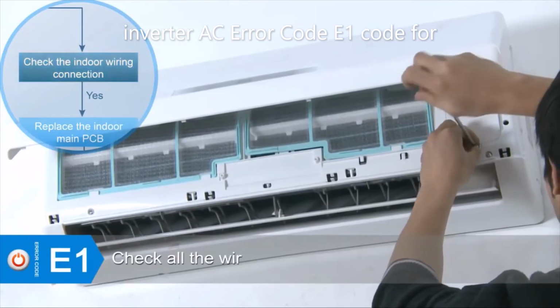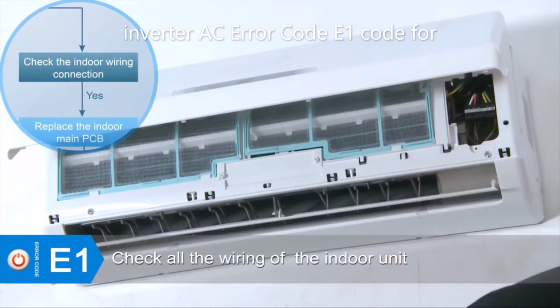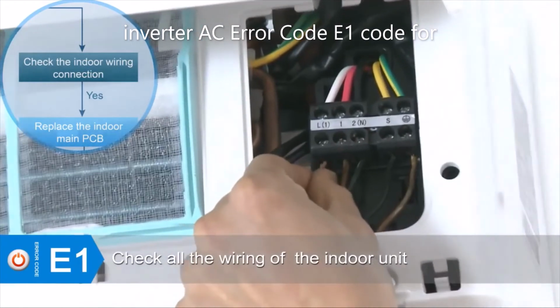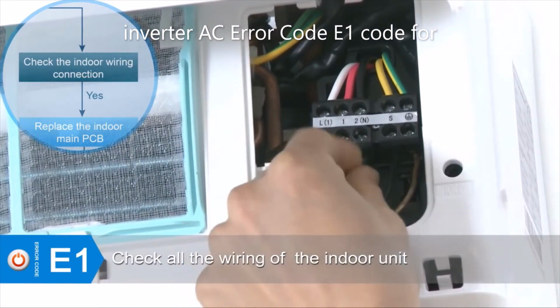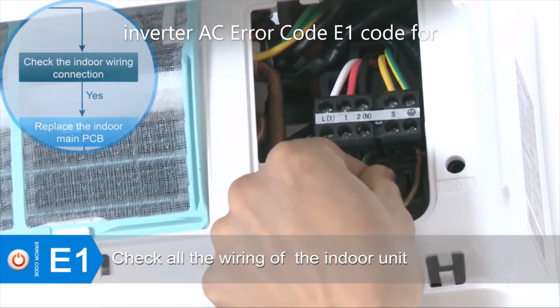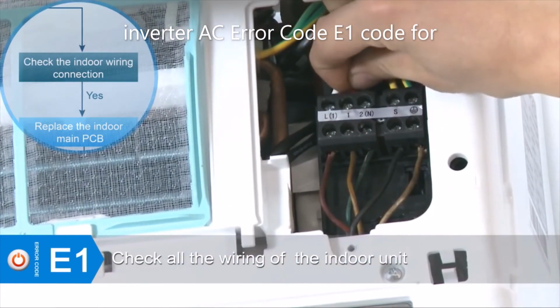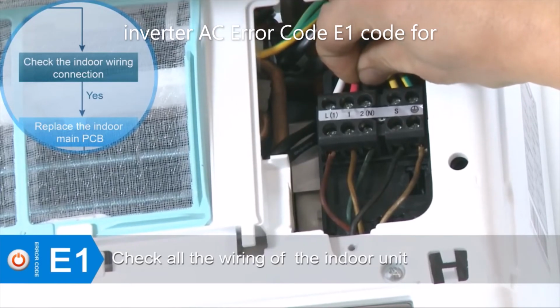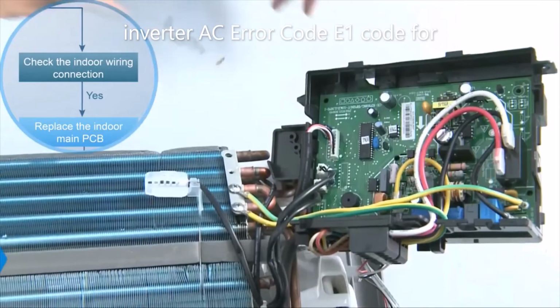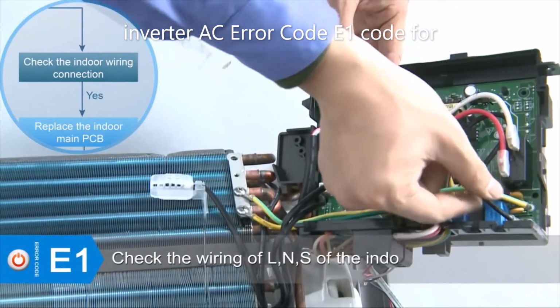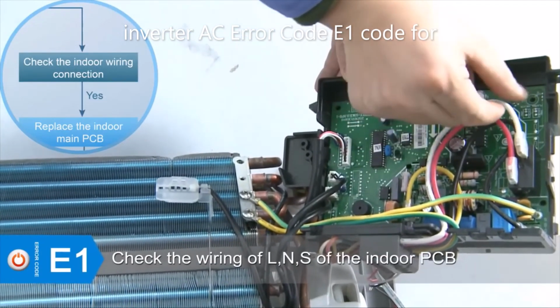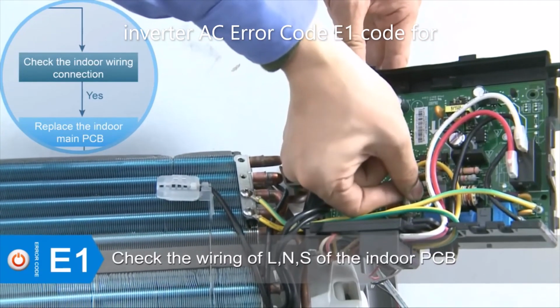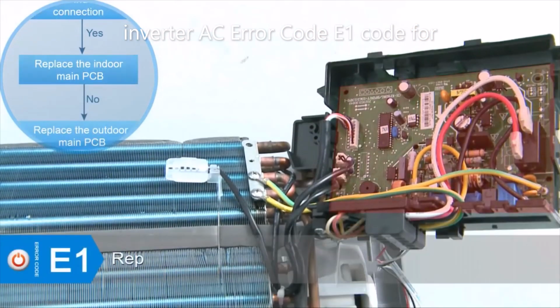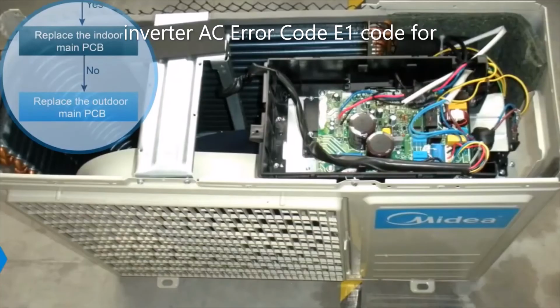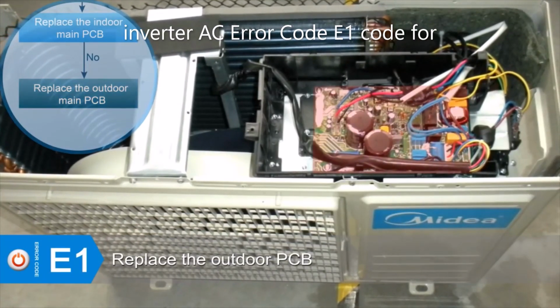Check the wiring of the indoor unit, which includes the power wires and the connecting wires between indoor and outdoor units. Check the wiring of L, N, S of the indoor PCB. If the error still exists after the maintenance above, replace the indoor PCB. If the error still exists, replace the outdoor PCB.